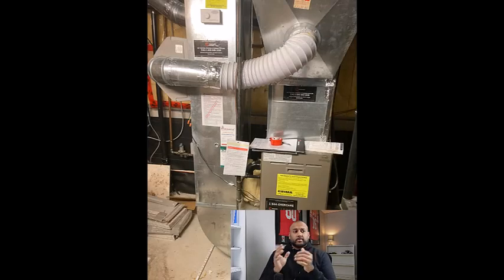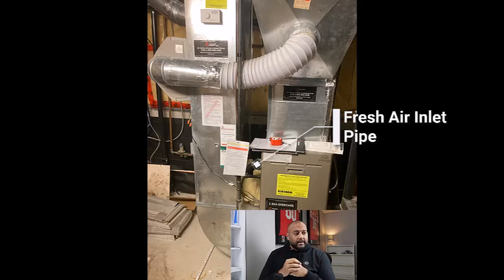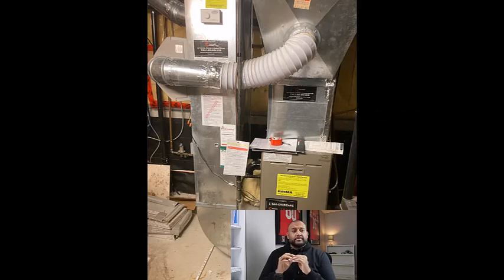So when we purchased our home, the basement was already finished, and one thing to note with a furnace like this, going back to that little pipe on the left that draws in the fresh air: when you don't have a finished basement, it pulls in all that circulating air throughout the whole basement, and it's able to get fresh air coming through there. Now, when you finish your basement, that area becomes enclosed around the furnace, and if you have a door on it, it's only pulling the air circulating within that furnace room, which is not really going to make your furnace that efficient. So what should have happened was, when the basement was finished, that pipe on the left should have been extended all the way out to the side of the house so that it can draw in fresh air from outside.